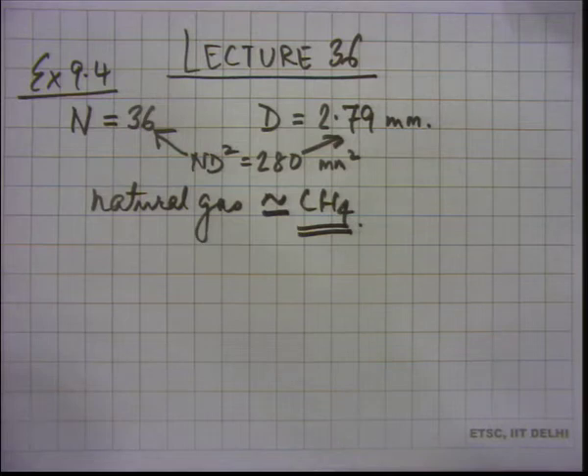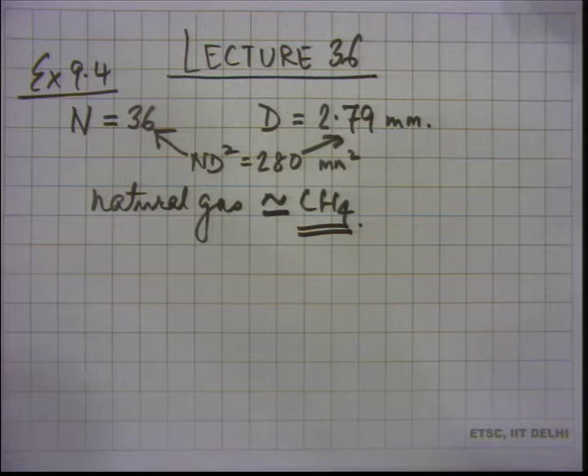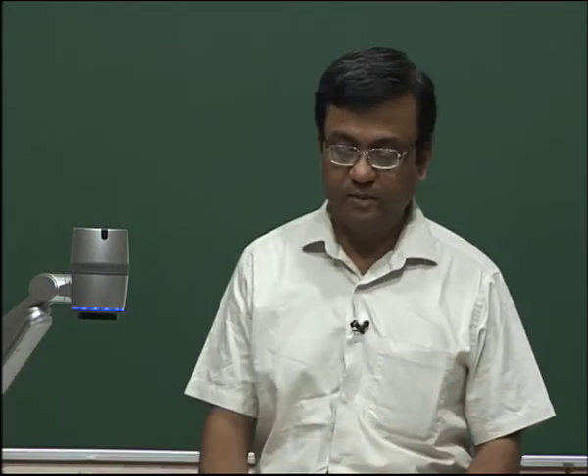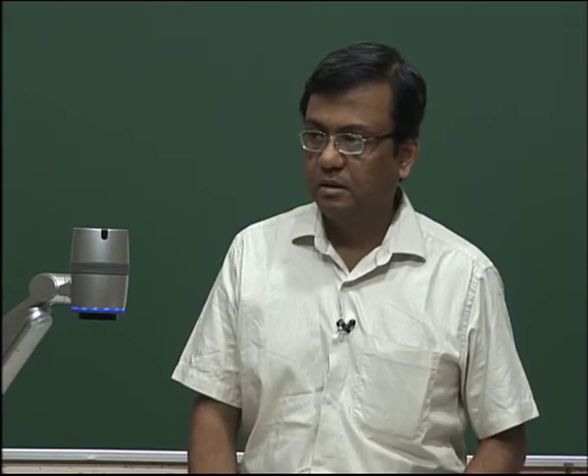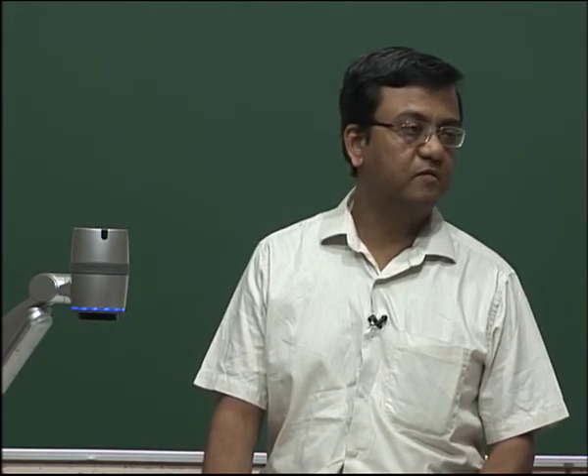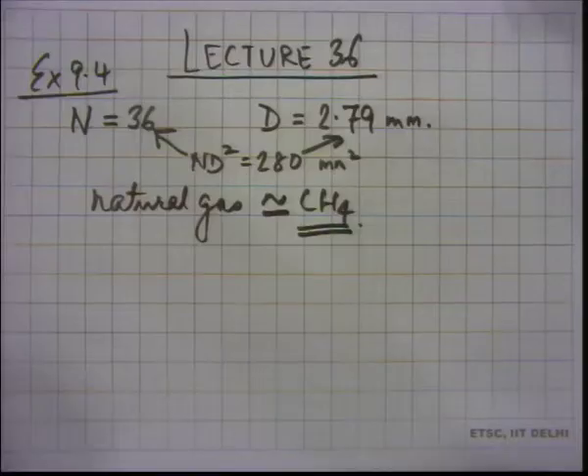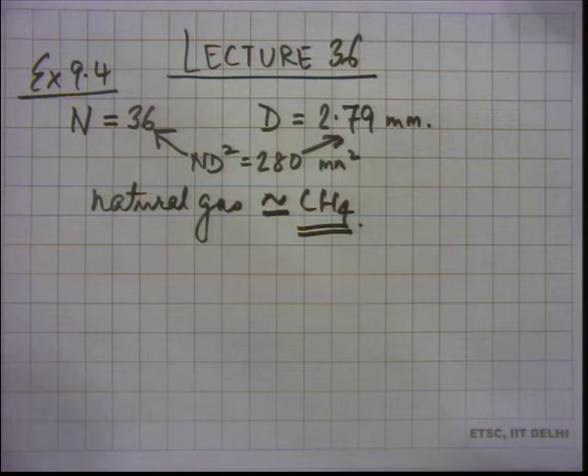Once we have the port diameter and number of ports, we need to check whether those values satisfy the constraints, particularly the flame length constraint. The flame length should not be more than 20 mm. To get the flame length, we need flow rates, because flame length is proportional to flow rate. The burner operating parameters give us 2.2 kilowatt and we have the port diameter, but we do not have flow rates yet — so we must calculate them.